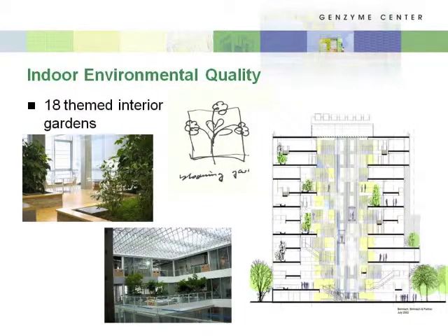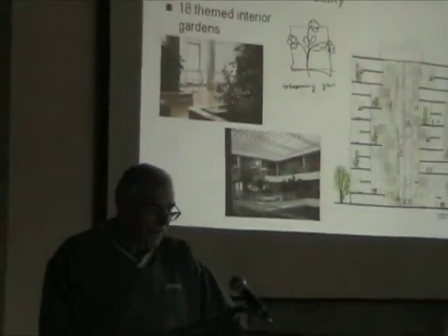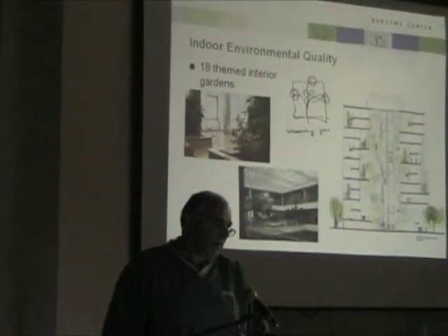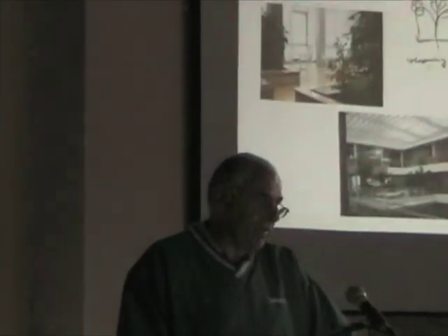Between the month of May and late October, between 10 p.m. and 4 a.m., if temperature outside equals temperature inside, wind speed is less than 10 miles an hour, and humidity is at the same level, all the windows will open up and flush out. It works pretty good. Last year we did it 14 times. In fact, we had an issue last night that they all opened up, which they should not have, because we had the temperature set for 74 degrees. So there's probably a glitch in the software end of it, and we'll have to look into it.